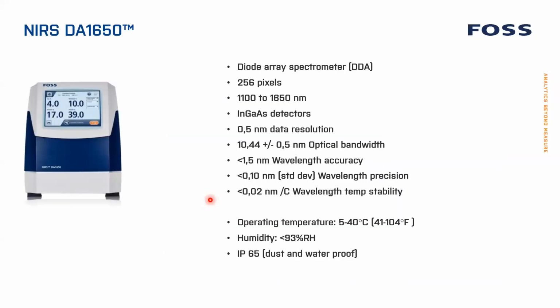DA1650. It's based on a diode array spectrometer with 256 pixels. This is the common configuration. It works from 1100 to 1650 nanometers, so it has a limited wavelength range. InGaAs detector, 0.5 nanometer data resolution, but the optical bandwidth is 10.44, so it's a little wider than a DS2500. And its wavelength accuracy is 1.5 nanometers, so it's not at all as good as the DS2500. And this is also the main reason why the transferability is not as good on a DA1650 as it is on a DS2500.